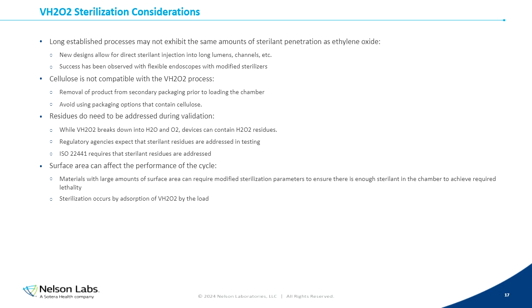And surface area, I have seen this in the lab. Surface area can affect the performance of the cycle. So materials with large amounts of surface area might require modified sterilization parameters to ensure there's enough sterilant in the chamber to achieve required lethality. One of the things that could affect it is if you, for example, are running a healthcare cycle with a lot of packaging material or wrap material, I have seen where that can affect delivered lethality. So you may have a situation where you need to run longer or more robust sterilization parameters to ensure that you're achieving sterilization.